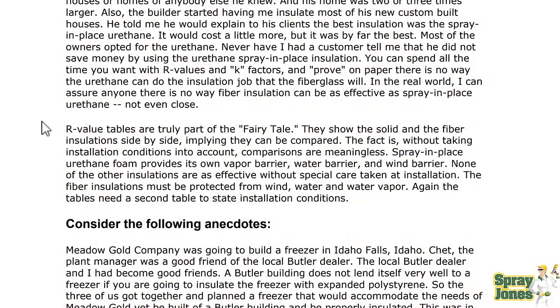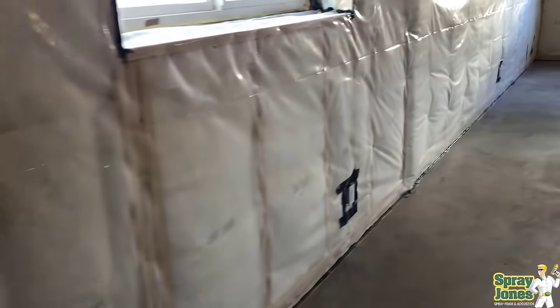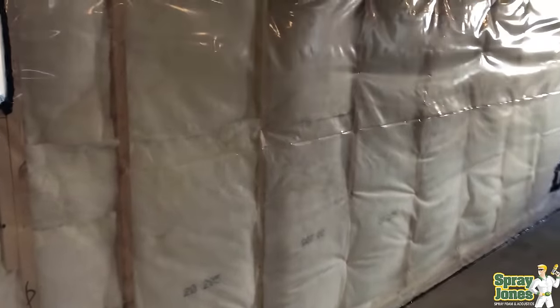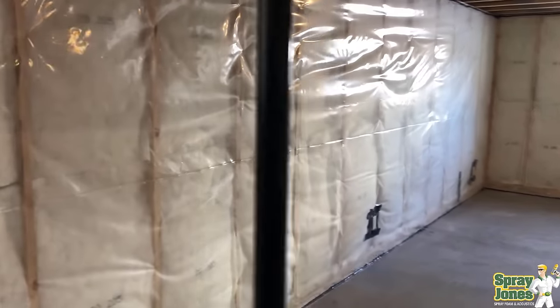R-value tables are truly part of the fairy tale. They show solid and fibrous insulations side-by-side, implying they can be compared. Without taking installation conditions into account, those comparisons are meaningless. Spray-in-place urethane foam provides its own vapor barrier, water barrier, and wind barrier — none of the other insulations are as effective without special care at installation. Fibrous insulations must be protected from wind, water, and vapor. The tables need a second table to state installation conditions. With fibrous insulation, unless you have physical contact on all six sides — top, bottom, front, back, left, right — the effectiveness goes down. You can lose 30% of your insulating ability just from installation anomalies.